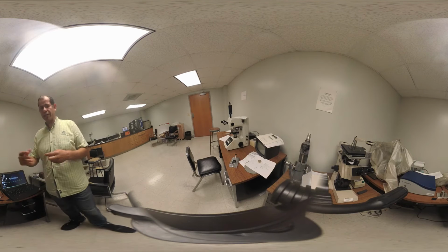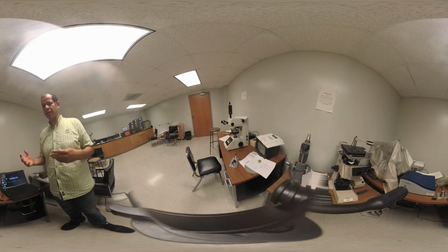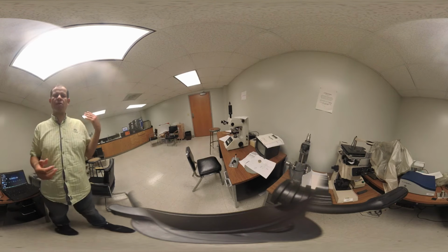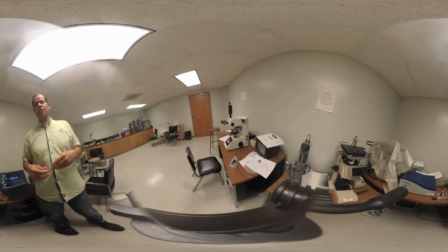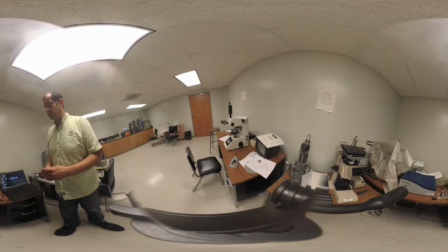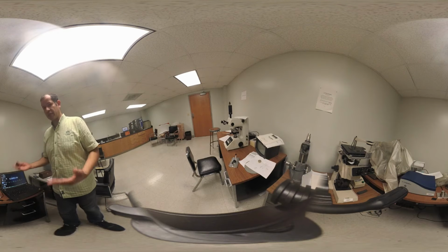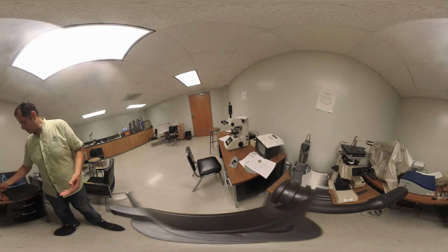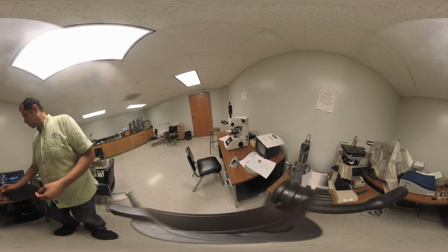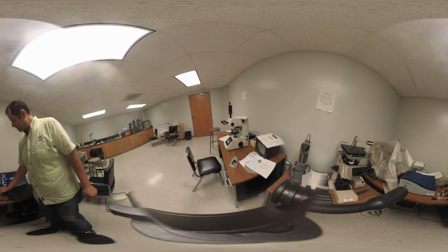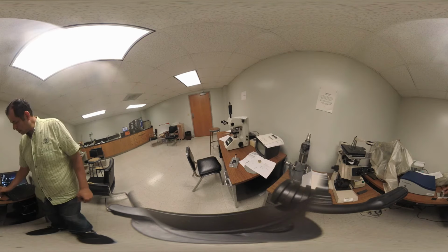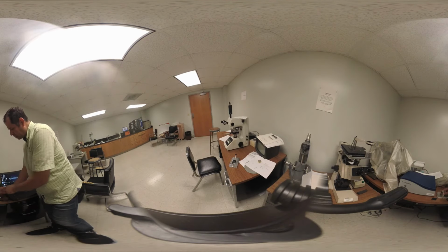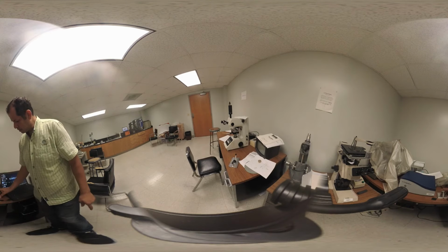You don't need to worry about the hand calculation or anything. You don't need to worry about the T hot and T surface, and also you don't need to do some preparation for the sample. Just add this sample here on this. It's called modified transient plane source, and there is a heater. You can see the heater. This one gets heat, getting a current. Apply a current from the C-Therm to the heater.